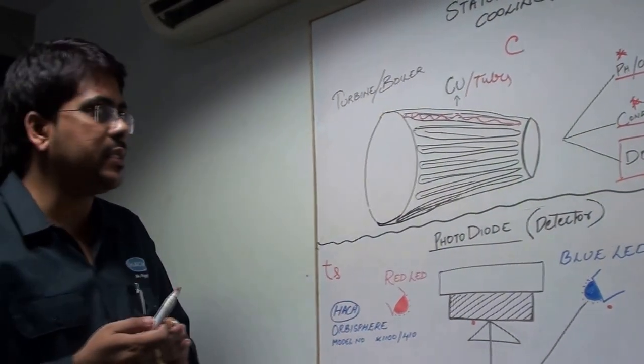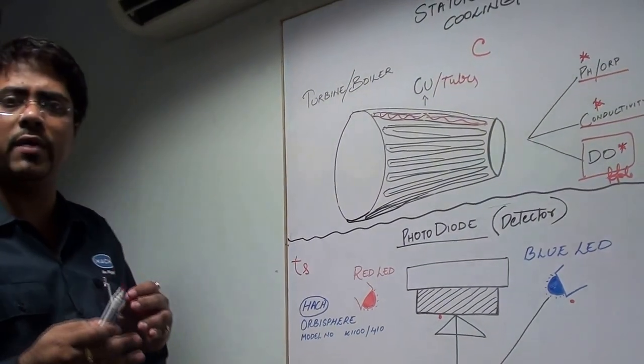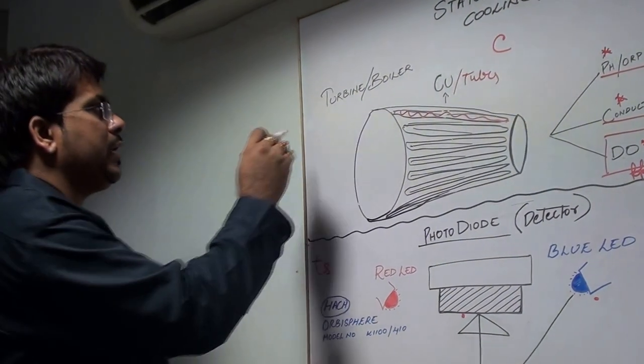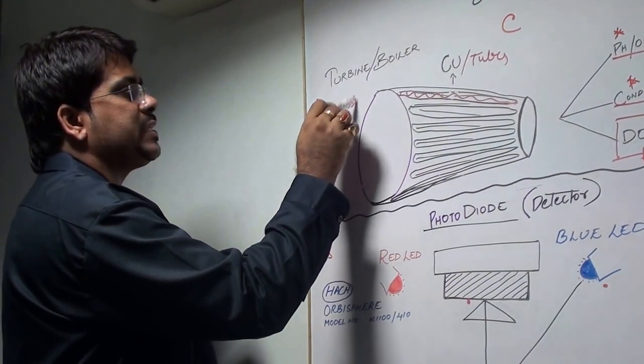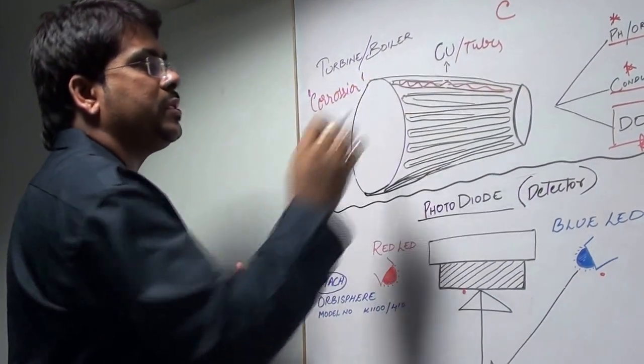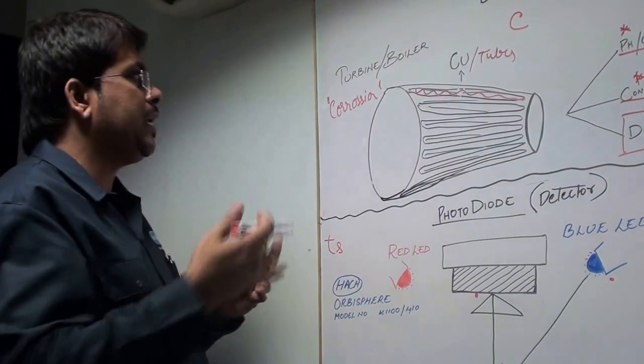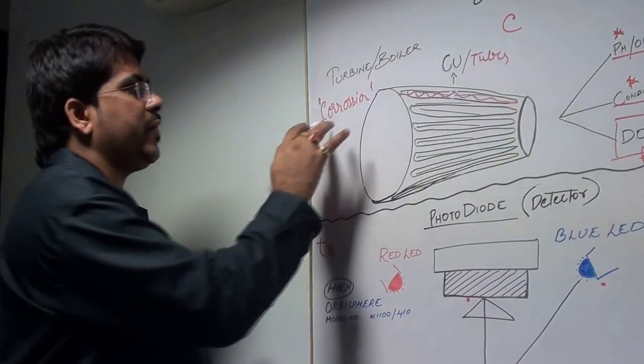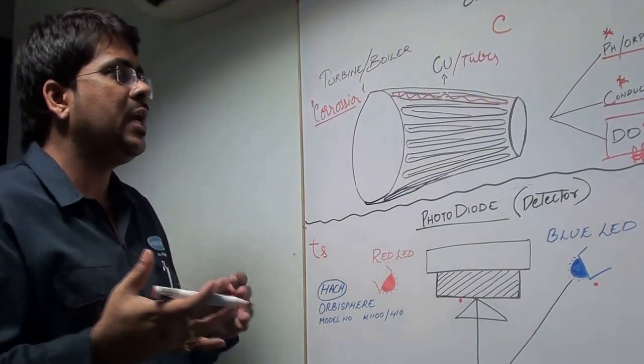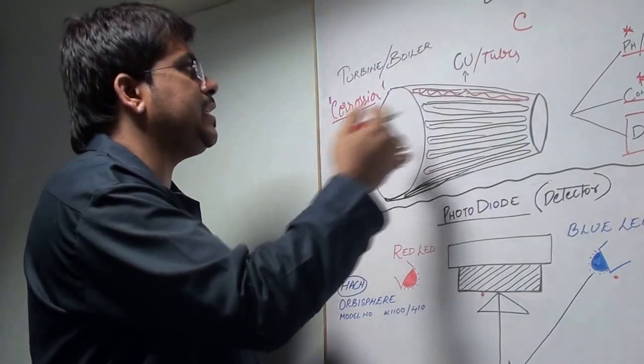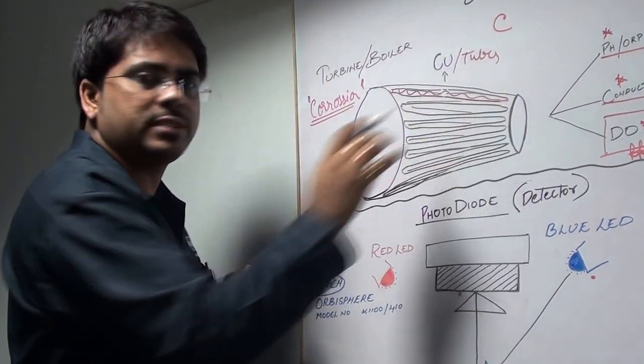Why is dissolved oxygen required? The most important phenomena we need to protect against is corrosion. These metallic copper tubes, when oxidized, will create the effect of corrosion. The presence of more oxygen will oxidize these and generate this corrosion effect on these tubes.